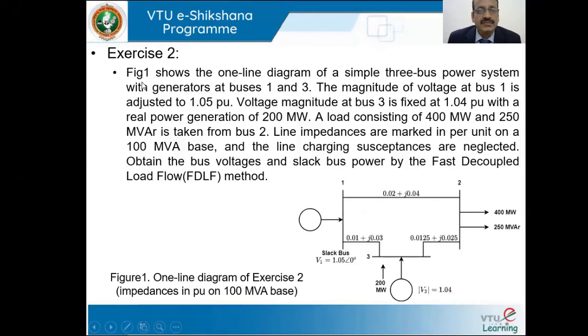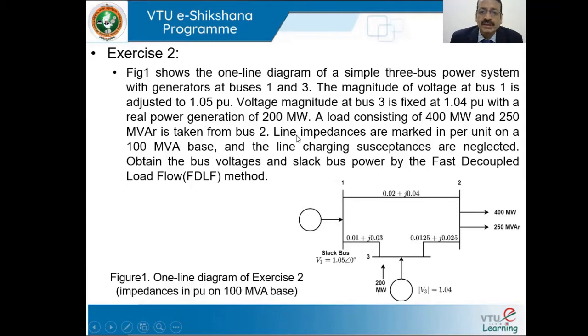This is the numerical which we had already considered to solve with the Newton-Raphson method. The figure shows a one-line diagram of a simple three-bus power system with generators at buses 1 and 3. The magnitude of voltage at bus 1 is adjusted to 1.05 at angle 0. Voltage magnitude at bus 3 is fixed at 1.04 with real power generation of 200 MW. The base MVA is 100 MVA, so 200 MW equals 2 per unit. A load of 400 MW (4 per unit) and 250 MVAR (2.5 per unit) is taken from bus 2. Line impedances are marked in per unit on a 100 MVA base and line charging susceptances are neglected. The objective is to obtain bus voltages and slack bus power using the fast decoupled load flow method.